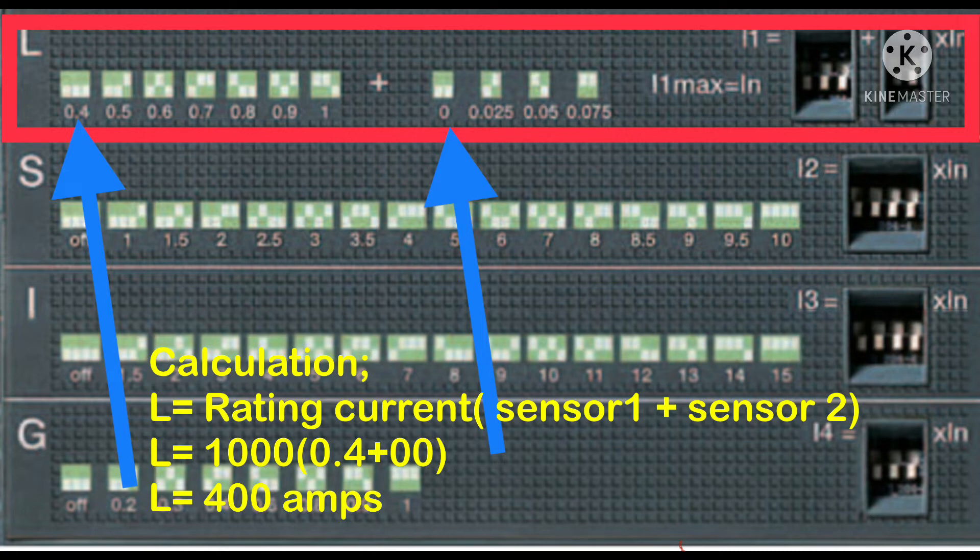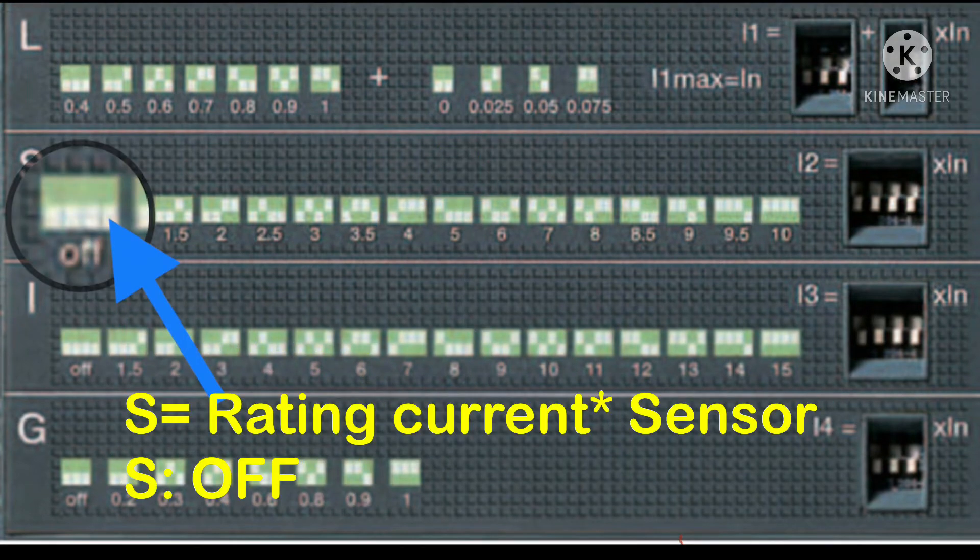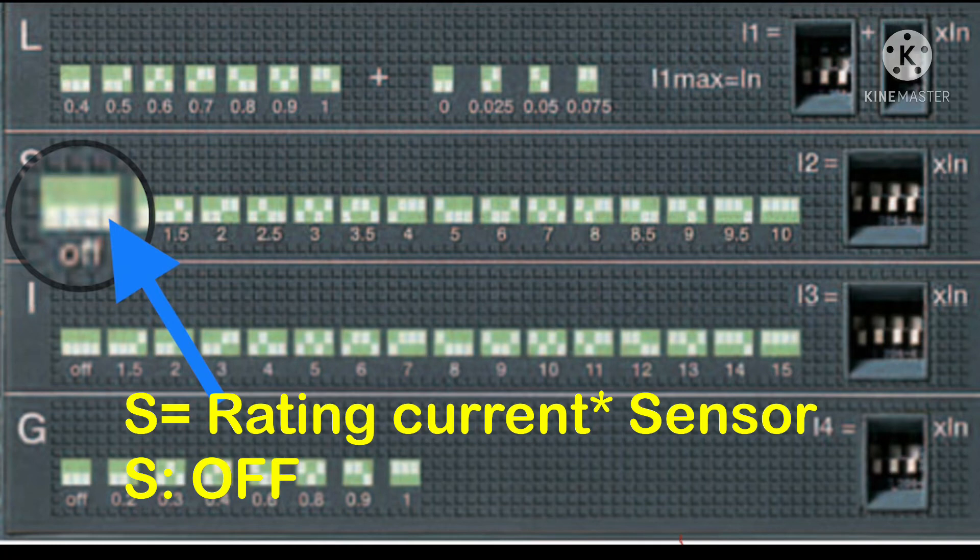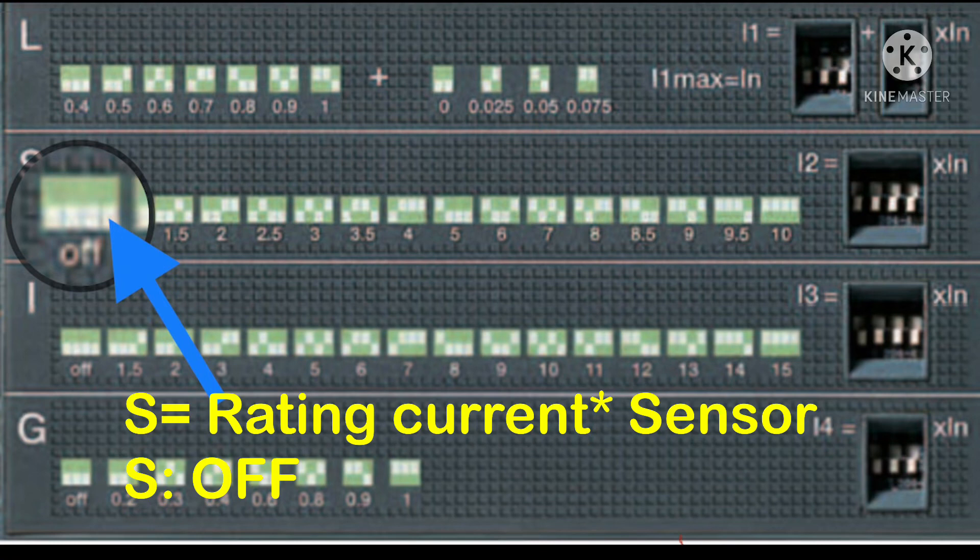That means our long time current for the breaker is 400 amperes. Now we will discuss short time current. The formula is rating current multiplied by the sensor. But here you can see the sensor is OFF, which means there is no short time current set in our breaker.